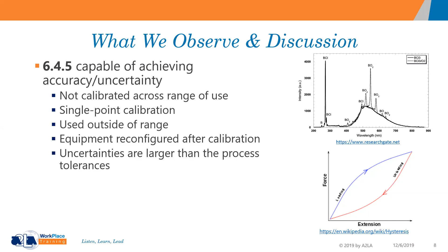And then the other thing that I see a lot of is that when people review the reports, they're not looking at the uncertainties. They say, yep, I got a calibration certificate by XYZ, it's accredited by ABC, and the uncertainties are a lot larger than their process tolerances. And of the 6.4.5 nonconformances, I would say probably about 10% ran into this. So please keep in mind that you have to be aware of the impact of the error or accuracy as well as the measurement uncertainty.